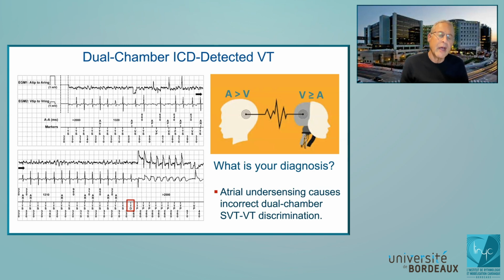The second is that the process of discrimination fails. And as we've just seen, it can fail at one of two levels. Broadly speaking, either there's something about the way the algorithm computes the difference between VT and SVT, the actual details of the morphology algorithm, or there's a sensing problem that prevents reliable determination of the rhythm, such as atrial undersensing or atrial oversensing or ventricular oversensing of T waves. Now, I haven't satisfied you with exactly what the secret sauce is of where each individual company's proprietary algorithms fail.